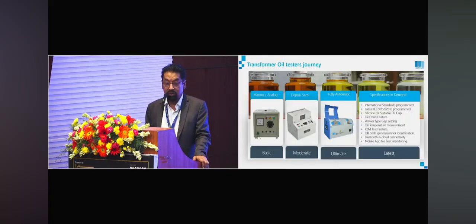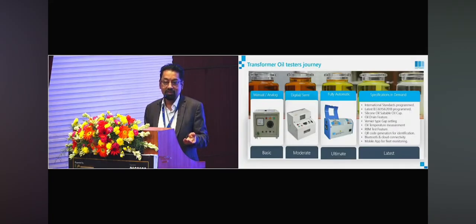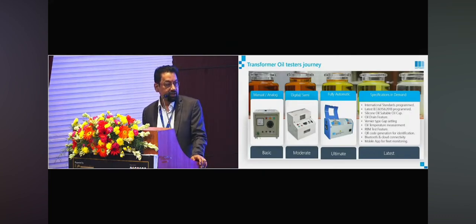And QR code, this is the latest demand. We have seen that when we go to the doctor and he does a blood test, a QR code is stuck on the bottle. But why was this not thought of for transformer oil? Now people are demanding it, because oil sampling bottles look the same, steel bottles. But how do you identify different oil samples with the transformer ID or the oil ID, so that the report can be correlated with it? How is that possible? With the latest technology, digitalization came into the picture. They want the QR code to be stuck on the oil sampling bottle. So this is what is changing the demand.